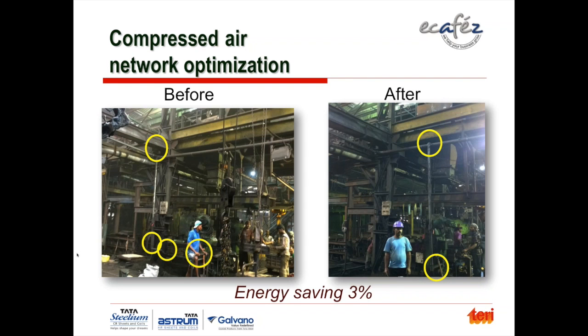The second energy saving area in a compressed air network is to design the compressed air pipeline properly. This photograph was taken from one unit where we did the audit. You can see a large number of bends. To take the compressed air line to the usage point, he had unnecessarily provided 4 bends, whereas it could have been done with 2 bends.